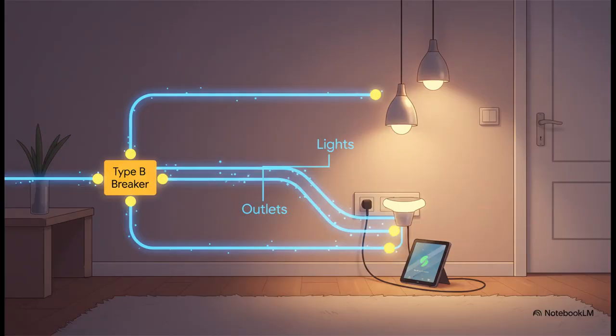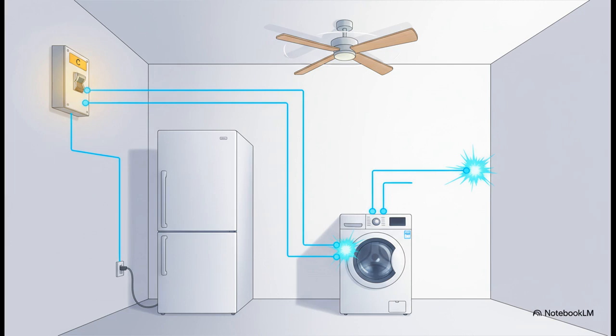First up, we've got Type B. Think of this one as this sensitive specialist. It's perfect for resistive loads, which is just a fancy way of saying things that don't have a motor, like your basic lighting circuits and standard wall outlets. Since they don't have a big startup surge, a really sensitive Type B breaker can protect them perfectly without tripping all the time.